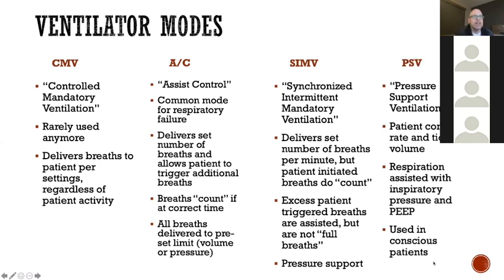The last mode I'll talk about on this slide is just pressure support ventilation, not something you're really going to see much of in an emergency department. This is where the patient is going to control their own rate and tidal volume. This is something we use more if we're going to be taking somebody off of a ventilator. So they've recovered in the ICU, we're getting ready to extubate them, and we want to see how they can do on their own. So we might do pressure support ventilation for a little bit. It gives them pressure on the way in and leaves pressure on the way out. But they're going to breathe on their own and take however big a breath at whatever rate they want. So this is basically BiPAP with an endotracheal tube. We're not going to do a lot of that, especially for an ARDS patient in the early stages.